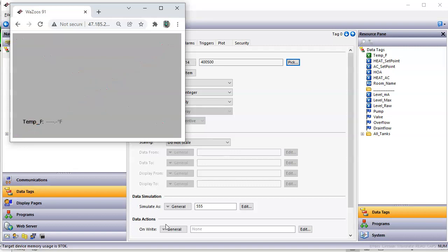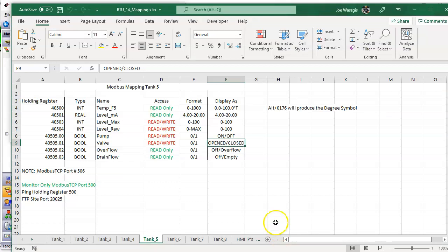All right, very interesting. Something different. Now, this one gives the dashed lines. That's when we're doing communications, testing comms to a PLC or something. The dashed lines means either the IP address is wrong, the cable's made wrong if we're doing it serially, maybe we got the pinouts wrong, the baud rate could be wrong, and so forth. Well, in this case, it's all over Ethernet. We know the IP address is correct, but this is dashed lines. So you might scratch your head and wonder what could it be?